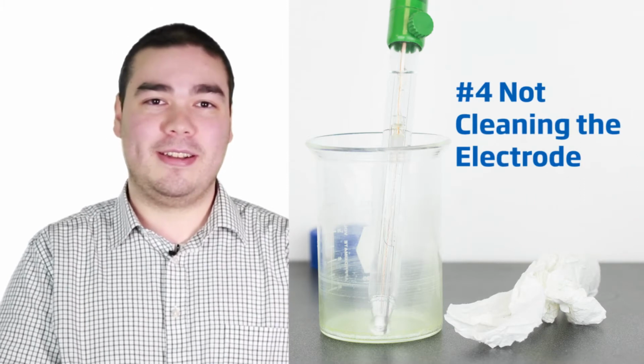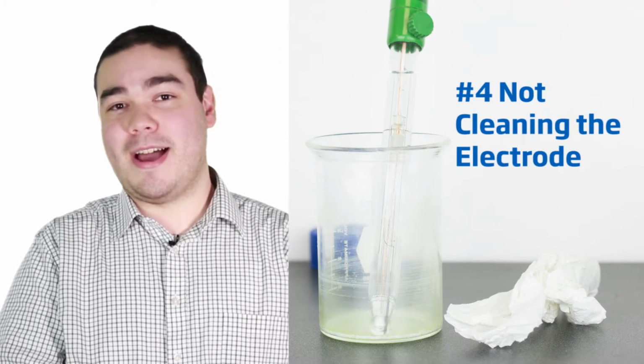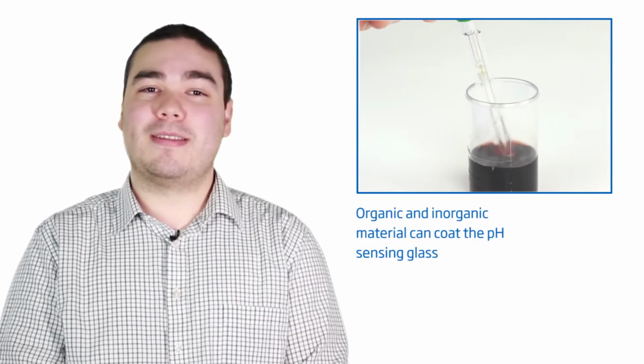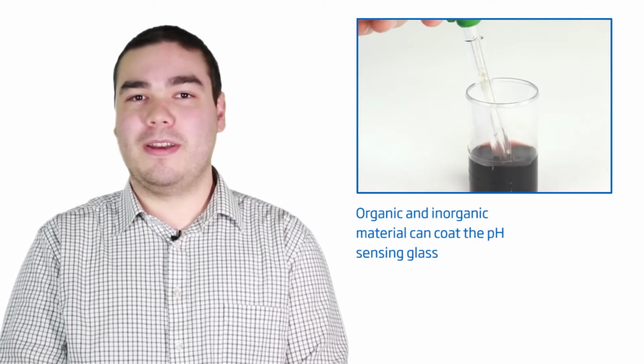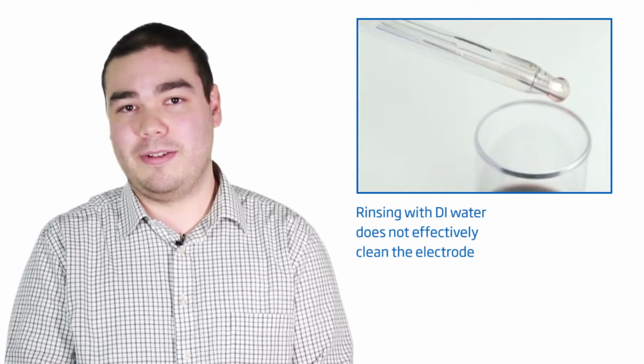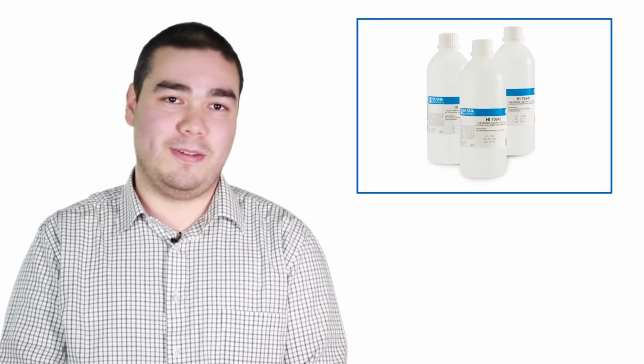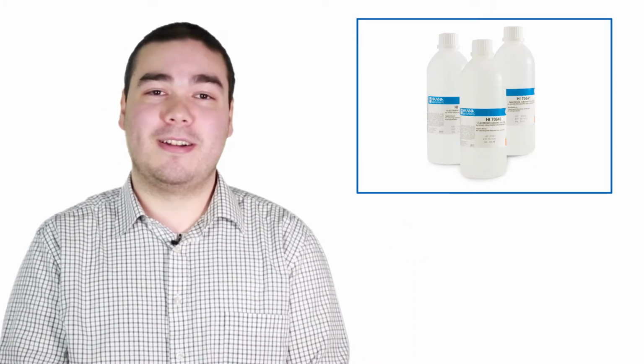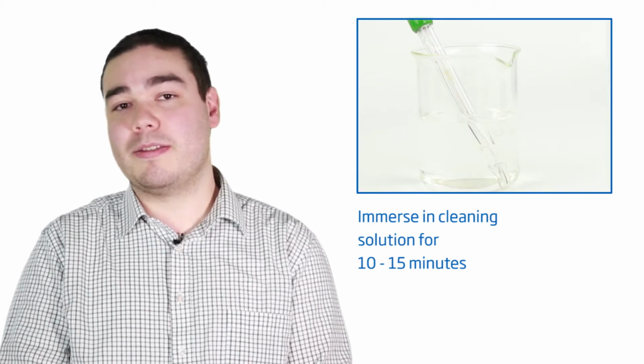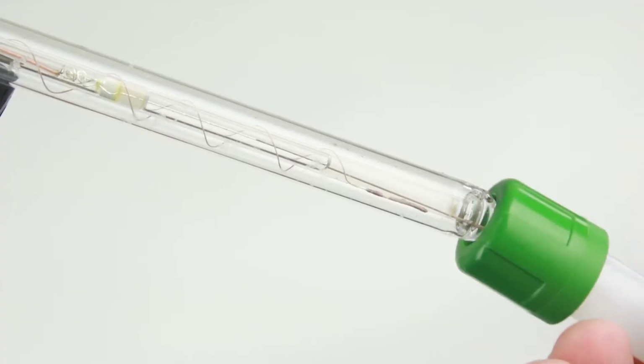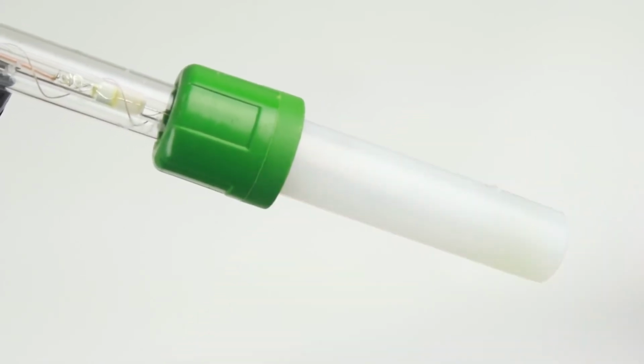That brings us to number 4, not cleaning the electrode. It doesn't take long for the electrode glass to form a dirty buildup. This buildup creates a barrier between the glass and the sample, causing readings to be inaccurate. Cleaning with distilled water alone will not remove the coating of some organic or inorganic materials. What you need is cleaning solution. Immerse your electrode in cleaning solution for 10 to 15 minutes before storing it away. After you've cleaned your electrode, keep the electrode capped in storage solution when not in use.